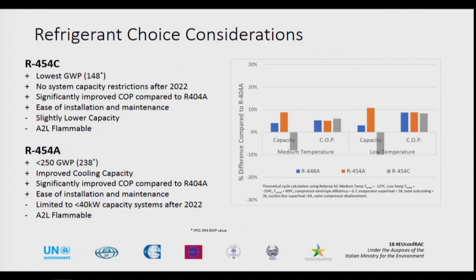Both options being looked at are A2L flammable, so there was some extra complication because of that. They also considered R454A, which has a slightly higher GWP of 238. That puts it above the F-gas 150 level, so there would be some need to control the size of systems to less than 40 kilowatts after 2022. But they also maintain the ease of installation and the energy efficiency gains they are looking for. So they eventually chose to look at the 454A as an option for their study.